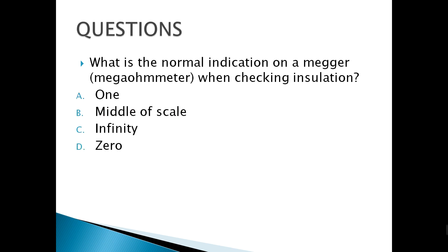What is the normal indication on a megaohmmeter when checking insulation? The megaohmmeter is used for checking very high resistance. For checking insulation, it should have a reading approaching infinity — a very high resistance.